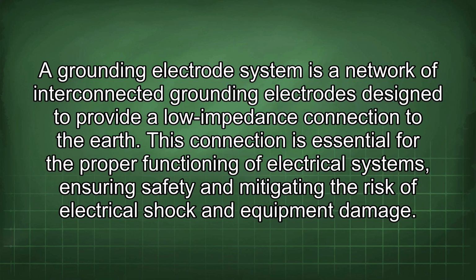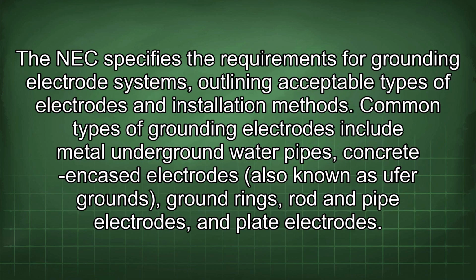A grounding electrode system is a network of interconnected grounding electrodes designed to provide a low impedance connection to the earth. This connection is essential for the proper functioning of electrical systems, ensuring safety and mitigating the risk of electrical shock and equipment damage. The NEC specifies the requirements for grounding electrode systems, outlining acceptable types of electrodes and installation methods. Common types of grounding electrodes include metal underground water pipes, concrete encased electrodes, also known as Ufer grounds, ground rings, rod and pipe electrodes, and plate electrodes.